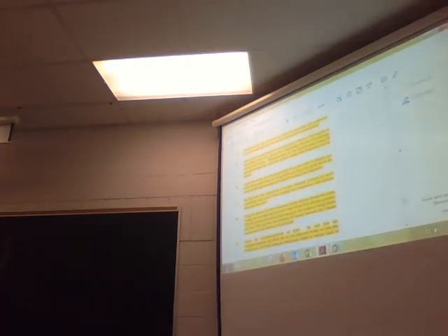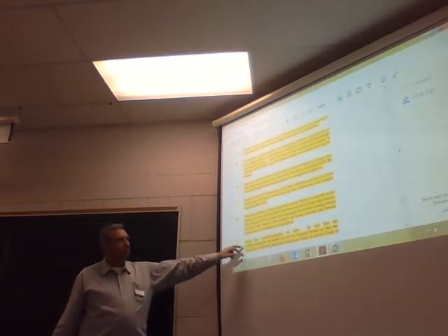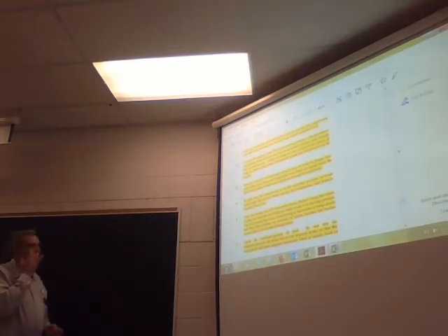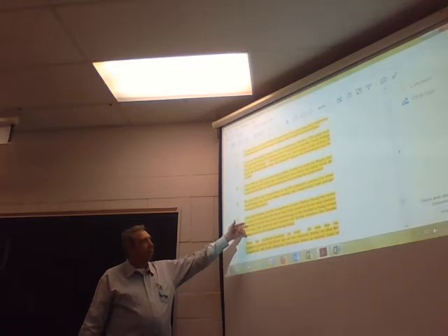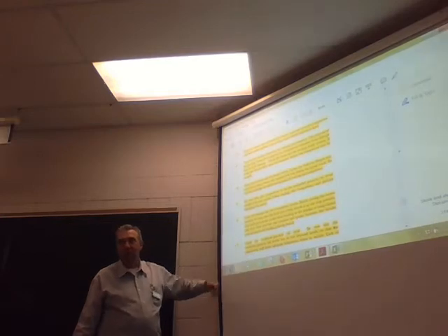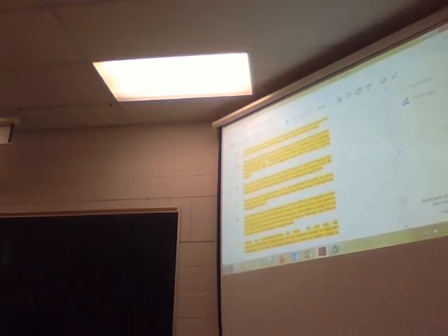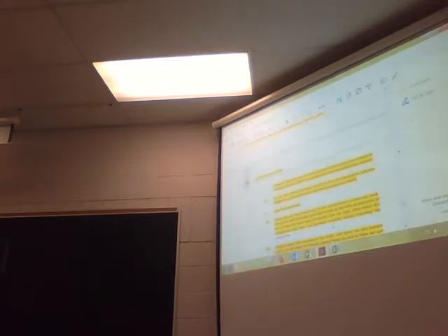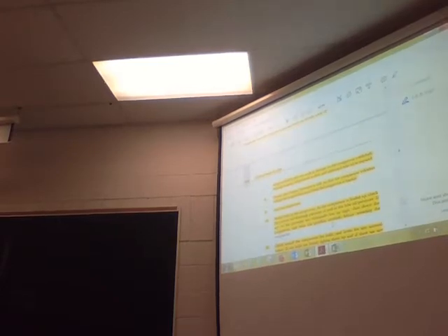Check the crankcase gear oil level. Be sure that the crankcase gear oil levels are at the required levels, so that the compressor will have adequate lubrication and service. If you do not have a stop-start switch, you're going to make sure the power is off when you do this. Well, if you don't know, they can automatically stop and start depending on load requirements, right? You want to make sure that there's no power to that when you're checking. Last thing you want to do is pull out a dipstick and check the oil with it live. Anyway, that'd be funny. If you're going to do that, let me videotape it. Ensure the cylinder lubricant is full so that the compressor cylinders get the proper lubricant.